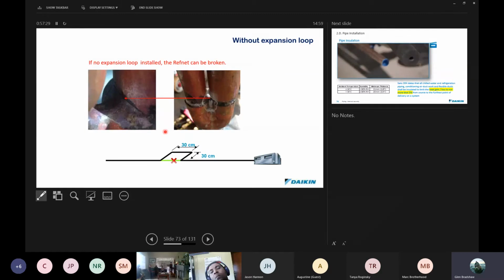This is the type of leak we're talking about in RefNets, where they crack in the Y joint, and that's often a telltale sign. If you've ever picked up a RefNet, you'll see that the welding is high quality and it's not likely to leak. Very often these leaks develop over time, and that's the giveaway that they didn't leak in the beginning but cracked over time. That tells us it was an expansion and contraction issue in the system. So just consider, if you need to use expansion loops, that is how they are to be installed.